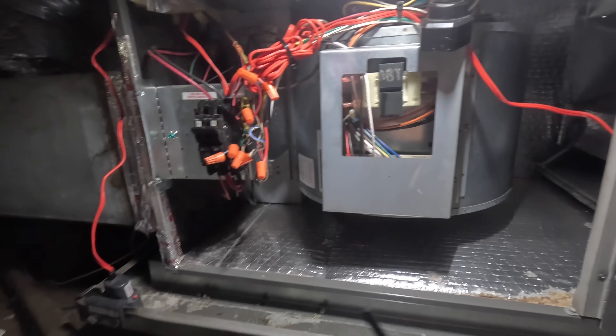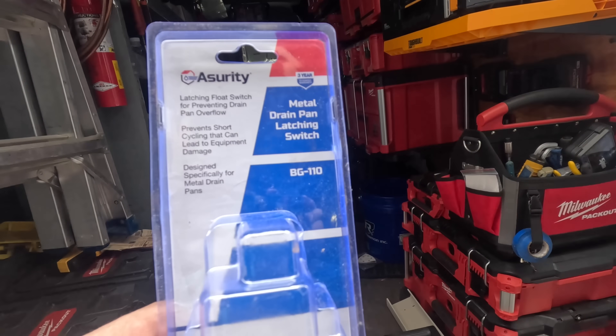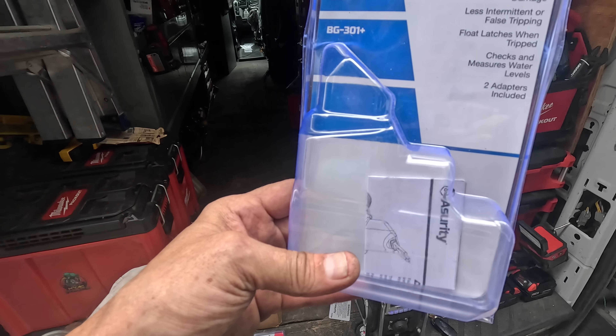Alright, this system's ready to go. Well guys, I hope you enjoyed that little video. These are the products I used — I'm going to be using these more often. This is the BG-110 by Asurity. And this is the one that I used to replace the SS2 — it's the BG-301 Plus. You're probably going to see a lot more of that one on my channel, because I like the way that it trips and causes a trouble call if it's backing up. You need to address it immediately instead of letting it reset and reset until it develops into a more serious problem. So I like those — I hope you enjoyed the video. If you did, how about like and subscribe and I'll catch you on the next one.